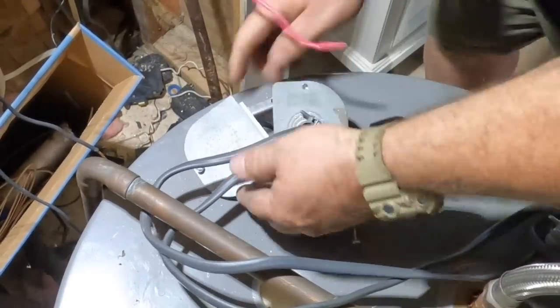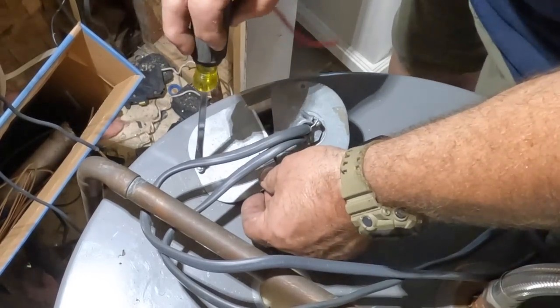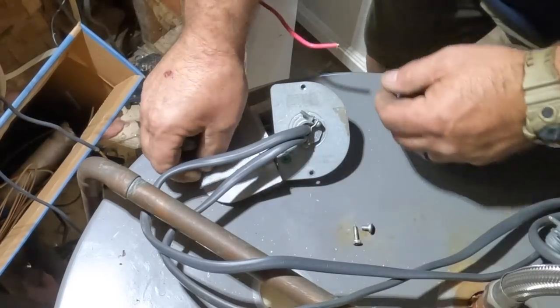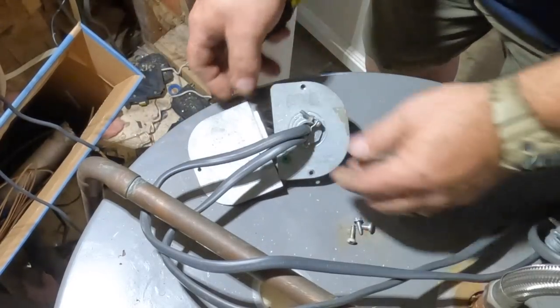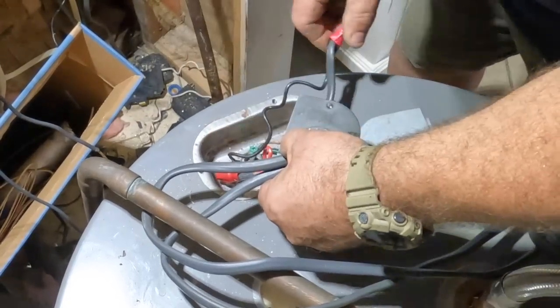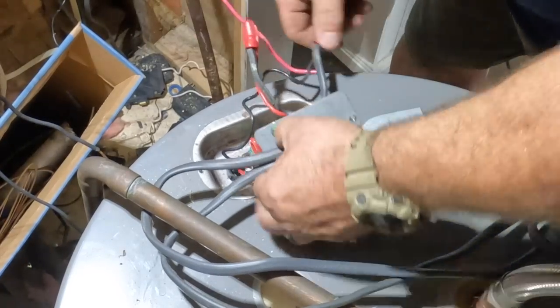Yes, so here you see this is a water heater with two pieces of 12-2 UF wire supplying the power to it. The homeowner revealed to me that he did this because that's the way it was before. So I said, let me correct this while I'm here. And it was a small upcharge to fix this. Really convenient way to do it now. This way he knows it's done correctly.